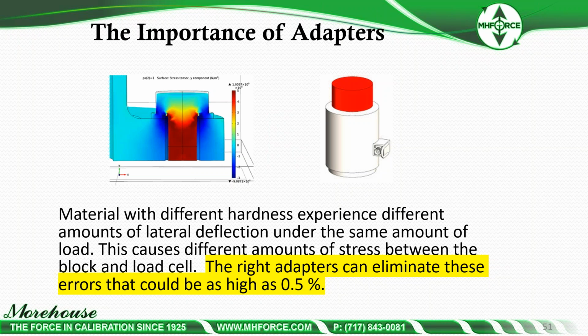I've done numerous tests with this. Hard blocks, the hardness of the material, make a huge impact on several cells. ISO is going to recommend top adapters. Just general good practice is to have a top adapter for that load cell, and that's what's in red up here. So have a top adapter that's sent in with that cell, and then have it calibrated with that, because you're going to harden that material. If it's soft material, over the lifespan of it, you're going to harden it. It should stay with the load cell.